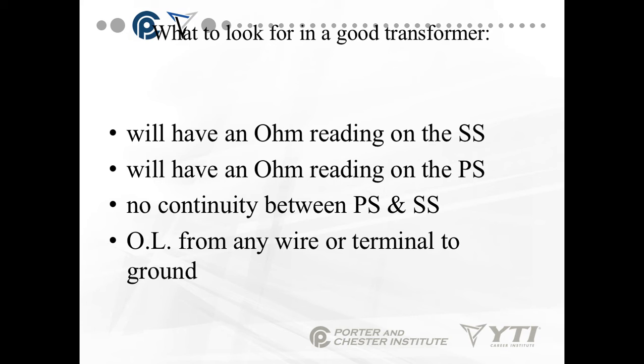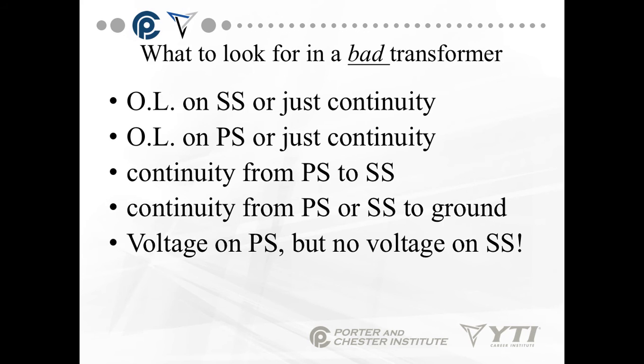In other words, if I put my ohm meter on one of the wires coming to the primary and put the other lead onto one of the secondary terminals, it should show OL. It should also show OL from any wire or terminal to the ground.